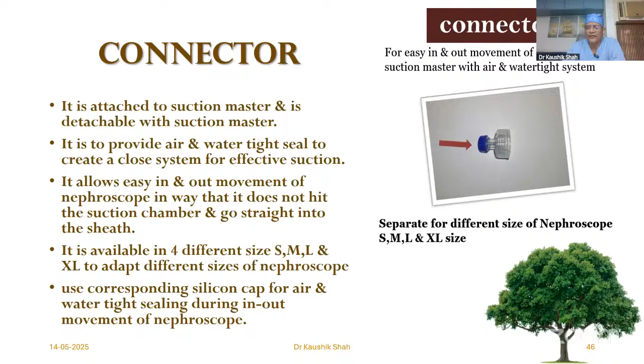Now, for the nephroscope not to hit the suction master, the lumen of the connector is designed in four different sizes, and it is labeled as S (small), medium, large, and extra large, so that different sizes of nephroscope can go in easily. They are marked on the connector, and therefore you have to use the corresponding silicone cap, and this links to the nephroscope for the easy functioning of the instrument.